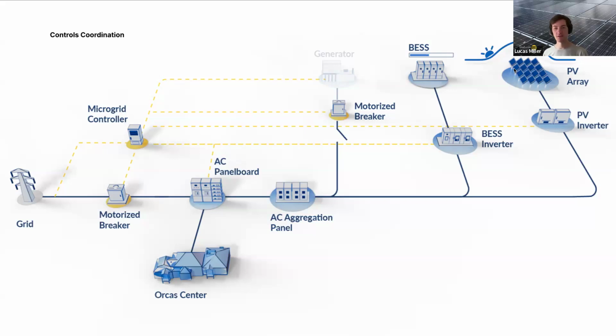So our PV array is just starting to kick online. Our BESS may have powered some of the facility loads overnight, so we're about halfway charged. We're still actively connected to the grid, so this motorized breaker is in the closed position. We progress through the day a little bit. Now we're midday. We've got a grid outage occurring here. So this motorized breaker tied to an electrical relay will sense a grid outage. It'll open this connection to the grid in an open transition.